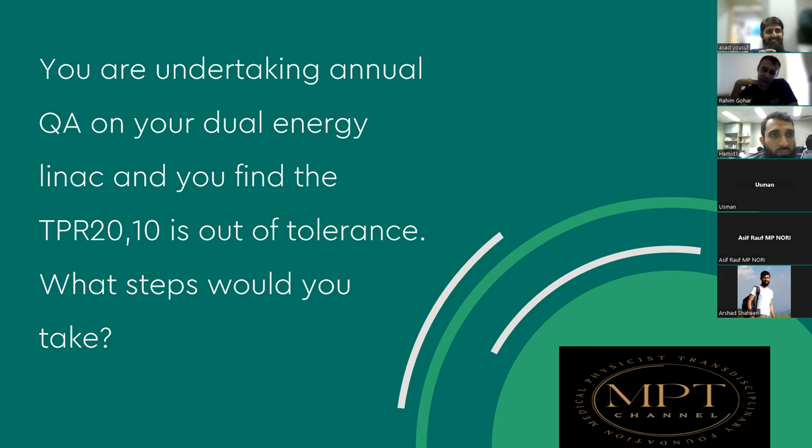Follow-up question. What's the importance of this TPR 20/10? It's verifying the beam quality. So beam quality is giving you what? Basically, it gives us what? It's basically the penetration power, the characterization of the energy, of course.